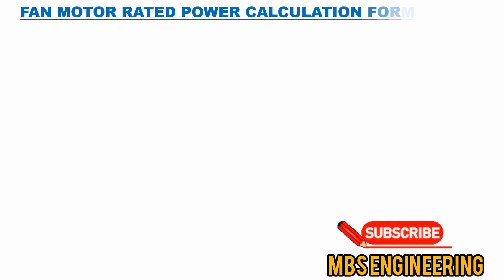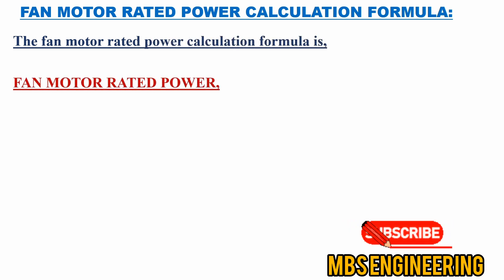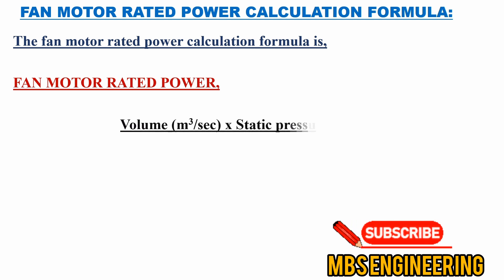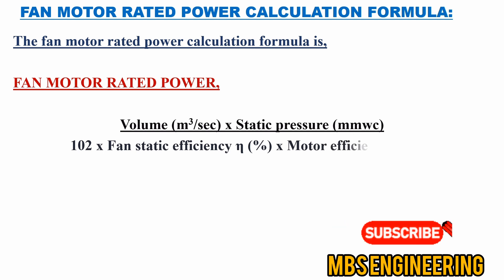We will learn and understand the formula used to calculate the fan motor rated power. The fan motor rated power is equal to volume in meter cubes per second, multiplied by the static pressure in millimeters of the water column, and the obtained value is divided by 102, multiplied by the fan static efficiency in percentage and the motor efficiency in percentage.